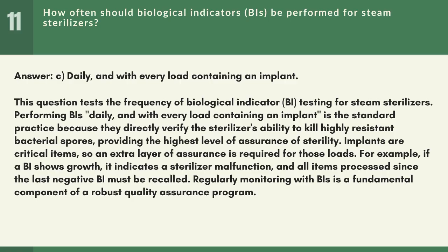Performing BIs daily, and with every load containing an implant, is the standard practice because they directly verify the sterilizer's ability to kill highly resistant bacterial spores, providing the highest level of assurance of sterility. Implants are critical items, so an extra layer of assurance is required for those loads. For example, if a BI shows growth, it indicates a sterilizer malfunction, and all items processed since the last negative BI must be recalled. Regularly monitoring with BIs is a fundamental component of a robust quality assurance program.